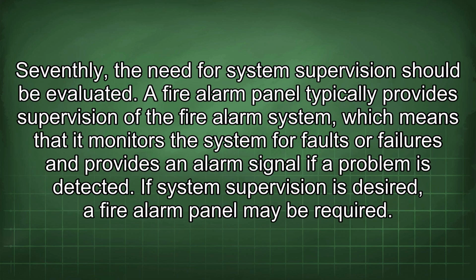Seventhly, the need for system supervision should be evaluated. A fire alarm panel typically provides supervision of the fire alarm system, which means that it monitors the system for faults or failures and provides an alarm signal if a problem is detected. If system supervision is desired, a fire alarm panel may be required.